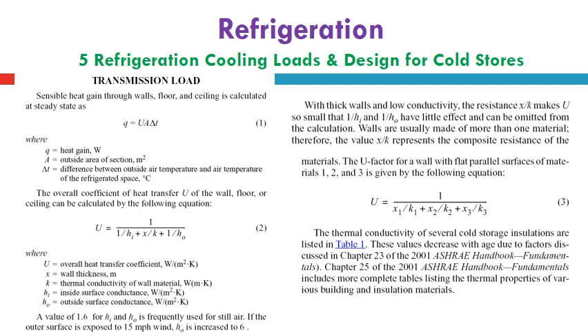This can be considered as natural convection, which can happen on the inside surface and the outside surface, just beside the wall from inside and from outside. So 1.6 watt per meter square Kelvin is a common value which may be frequently used for this application.